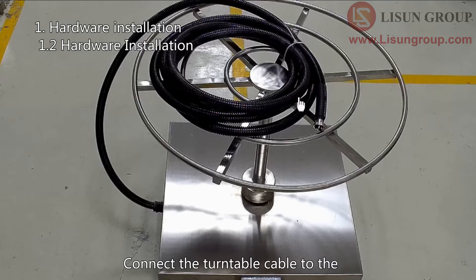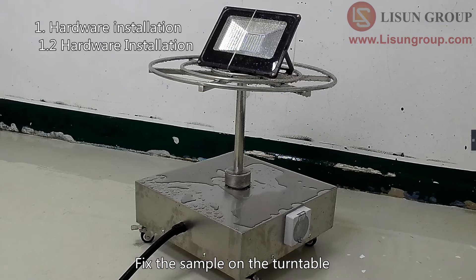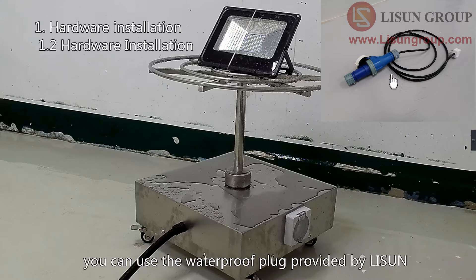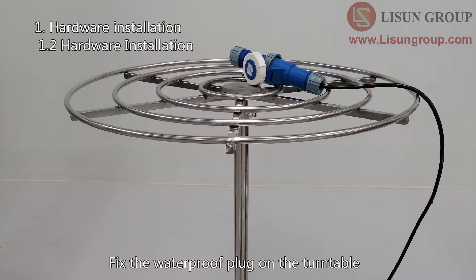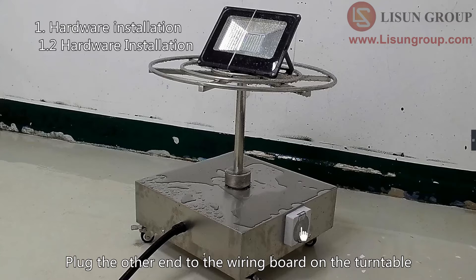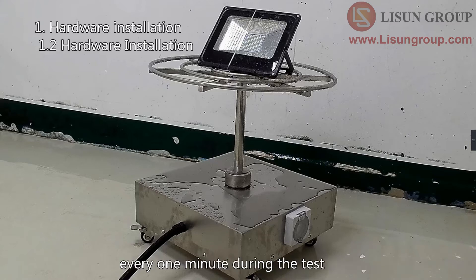Connect the turntable cable to the corresponding socket on the water tank. Fix the sample on the turntable. If the sample needs to be turned on during testing, you can use the waterproof plug provided by Lisun. Fix the waterproof plug on the turntable and connect your sample to the plug. Plug the other end into the wiring board on the turntable. The turntable will automatically change the rotation direction every one minute during the test, so the cable will not be entangled.